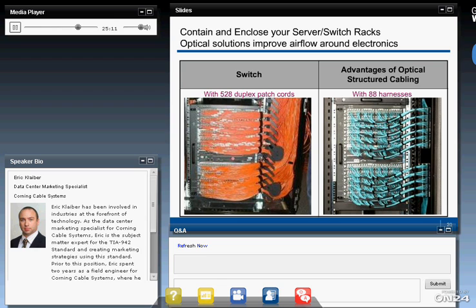These are two pictures of a Cisco 9513 with the maximum amount of fibers connected to it, which is 528 fibers. Actually, it's over 1,000 fibers, because there are duplex patch cords there. So what you see is the amount of bulk that the cabling jumpers can block airflow. This is a side breather, so we have to have air come from the left and go to the right. And the one on the right-hand side is actually the harnesses. So the harnesses allow you to get better airflow, have ease of connectivity, and you can actually pull a switch out without affecting any of the other switches, or any of the other blades, which is difficult to do with the jumper solution on the left.